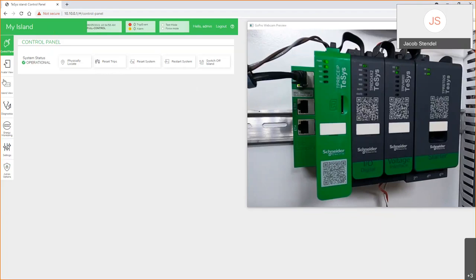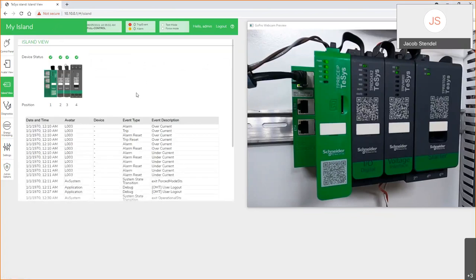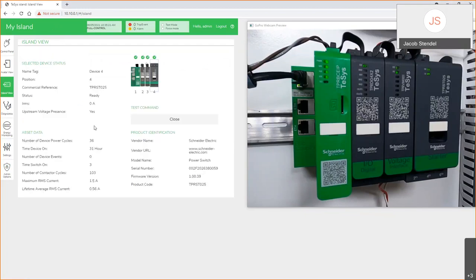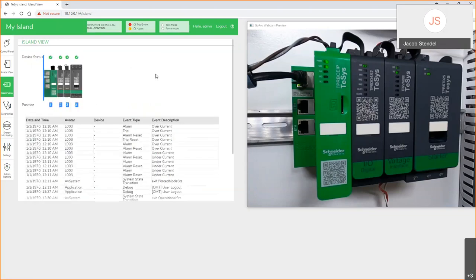I'm going to go to the island view first. This is currently showing you the live island and all the available alarms that I've run into and used on my demo unit here. The tabs on the left are all your navigation tabs. This is how we interact with it. Click on, for example, the different modules. You can see what's currently going on: the power cycles, the contactor cycles, your max power, your runtime. These are all really important feedback and information that you don't get with a traditional contactor system.